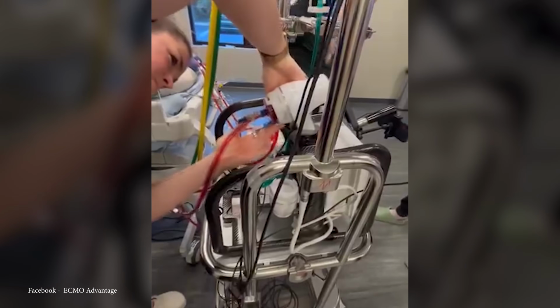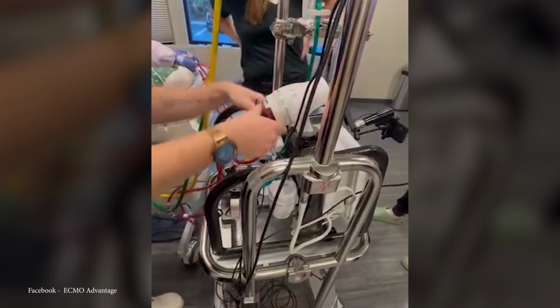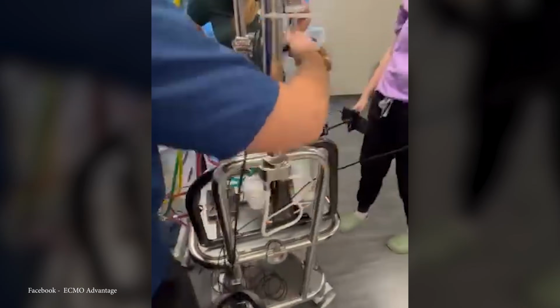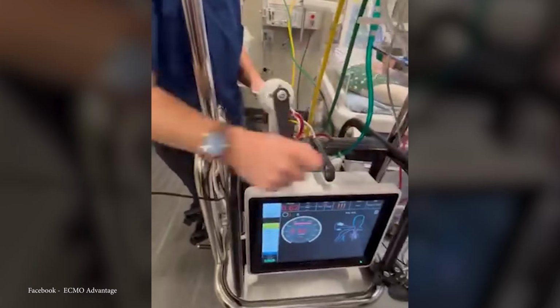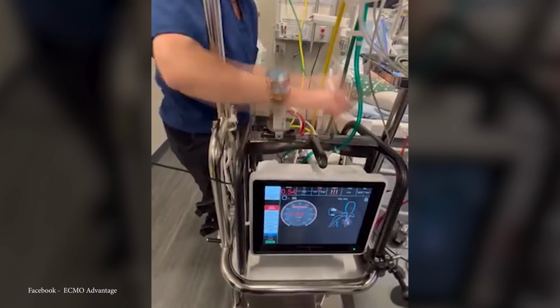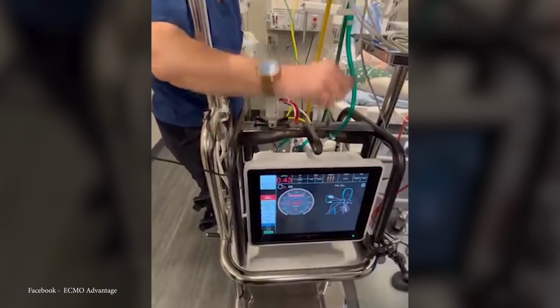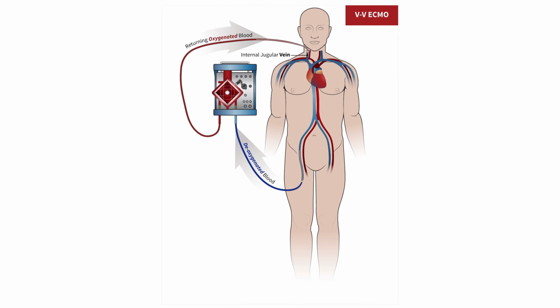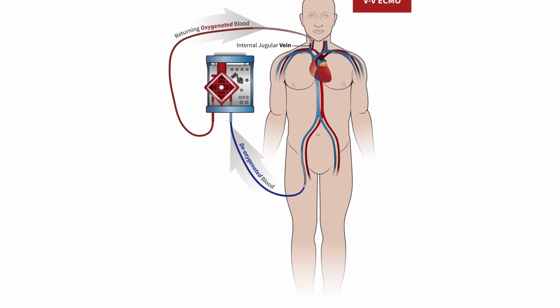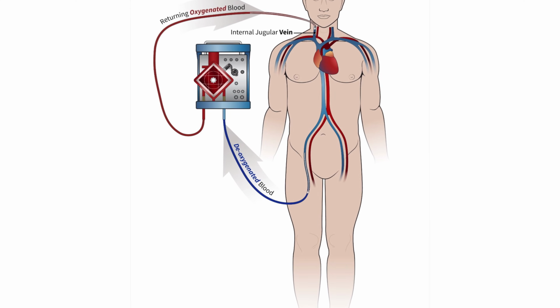An ECMO system works by removing blood from the patient through large cannulas inserted into major blood vessels. The blood is pumped through an external circuit to a membrane oxygenator, where carbon dioxide is removed and oxygen is added. This oxygenated blood is then returned to the body, and this entire process happens continuously outside the patient's body, sometimes for days or even weeks.